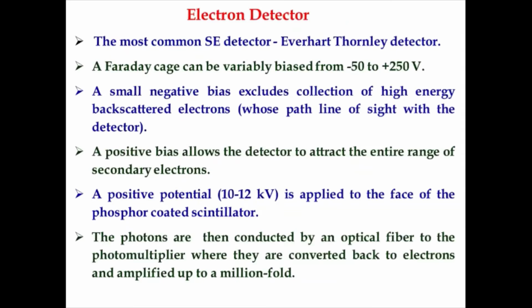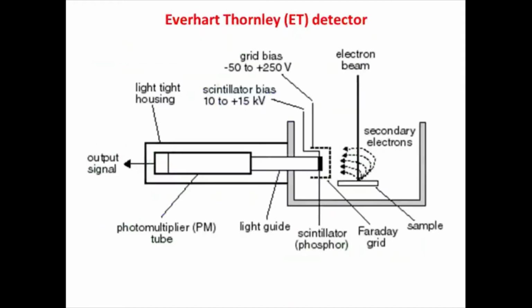Although there have been advancements in the electronics of the machine, means software, image analysis, image gathering, or on electron focusing, lenses side, but the detectors, there is little development. The most commonly used detector in the scanning electron microscope is the Everhart-Thornley detector to detect the secondary electrons. So basically, it is a scintillation based detector.